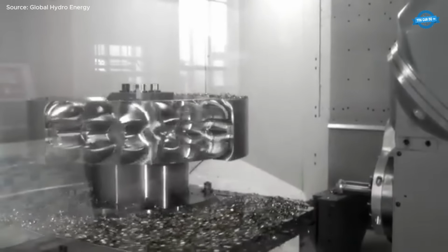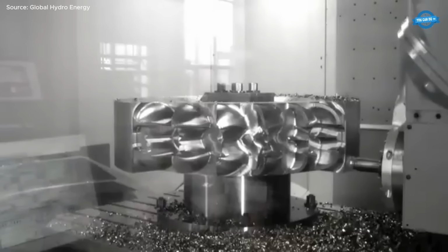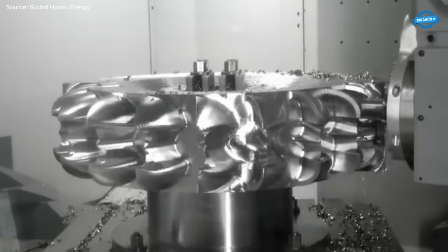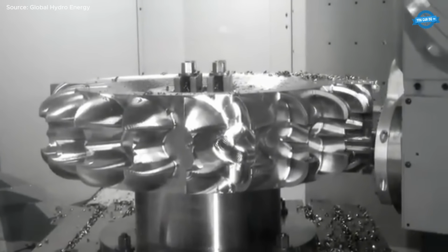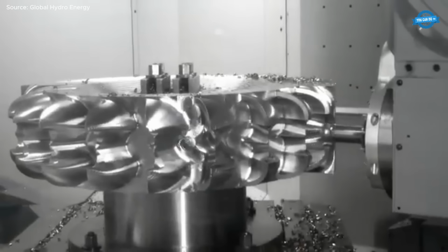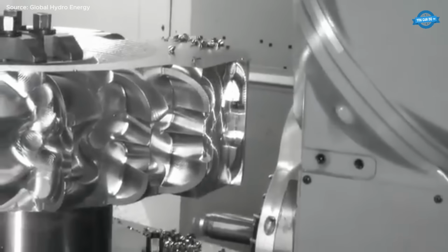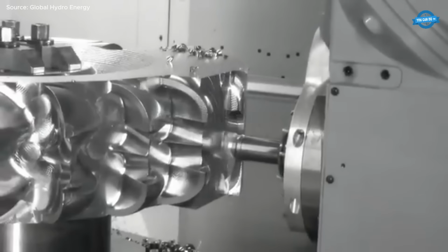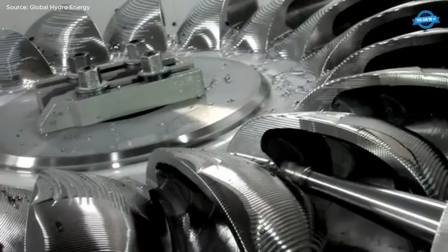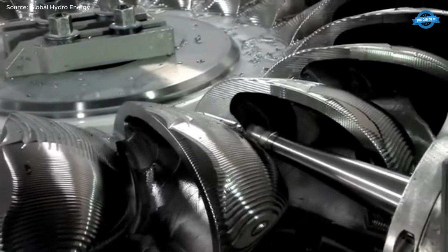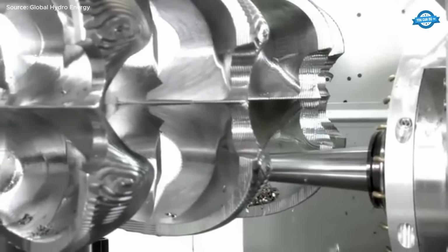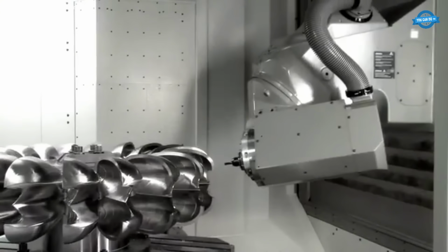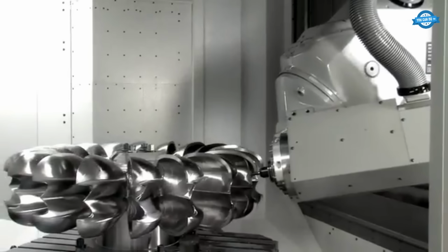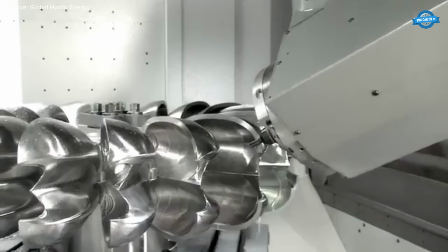A monoblock disc of high-grade stainless chromium nickel steel undergoes strict material inspection before machining. The runner is then milled on a 5-axis computer numerical control machining center, where complex bucket geometry is rough machined, then finish milled with simultaneous multi-axis movements. Programming and simulation ensure accurate tool paths and collision control. Grinding, polishing, and static, as well as dynamic balancing, complete the process. The result is a high-efficiency Pelton runner engineered for durability, repeatability, and long-term operational stability in small hydropower plants.